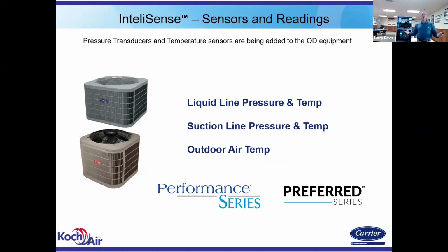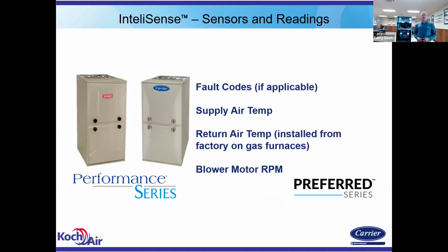So again, the outdoor, we're gathering suction and liquid pressures, suction and liquid temperatures. It'll calculate superheat and subcooling for you, and you're looking at an outdoor temp. On the indoor furnaces, fault codes, if there's any, supply air temperature, return air temperature, and blower RPM. So on the furnace, return air temp's already wired, just a little pigtail. It's right here in the return housing. The supply air temp sensor comes taped to your Z-tube right there. You'll install that after your cooling coil. If you install it before the cooling coil, you won't know what your supply air temperature is in the cooling mode. You won't know if your AC is working right. So that's going to install downstream of the cooling coil.